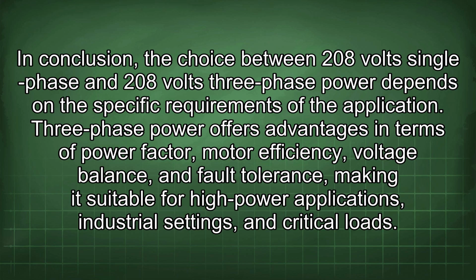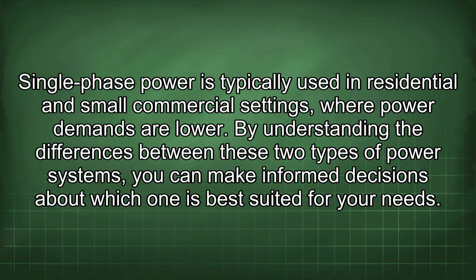In conclusion, the choice between 208V single-phase and 208V three-phase power depends on the specific requirements of the application. Three-phase power offers advantages in terms of power factor, motor efficiency, voltage balance, and fault tolerance, making it suitable for high-power applications, industrial settings, and critical loads. Single-phase power is typically used in residential and small commercial settings where power demands are lower. By understanding the differences between these two types of power systems, you can make informed decisions about which one is best suited for your needs.